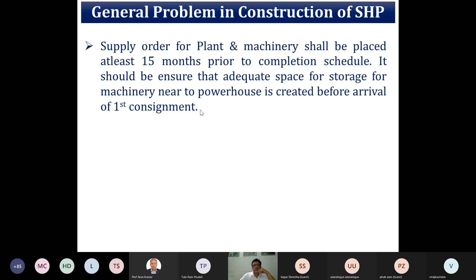This is because placing the order too early will lead to IDC. If you place the order at the very start of the project, the money required for this is significant, as the E&M equipment supplier will demand an advance, and once he manufactures all the machinery, he will ask for transportation as well. So, for loading and unloading heavy equipment such as the generator, turbine, and butterfly or spherical valves, a crane should be installed inside the powerhouse before their arrival.